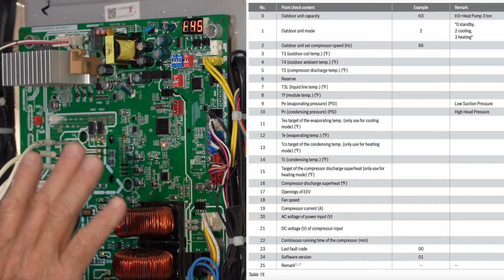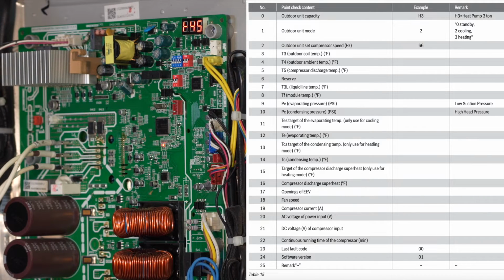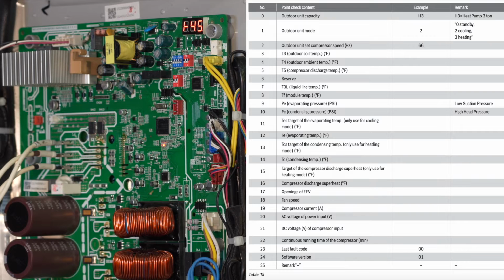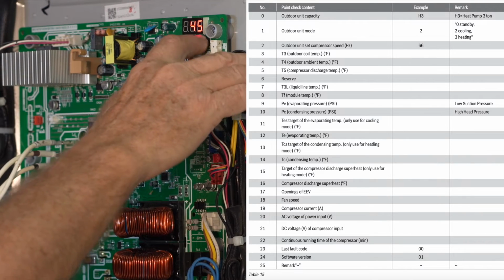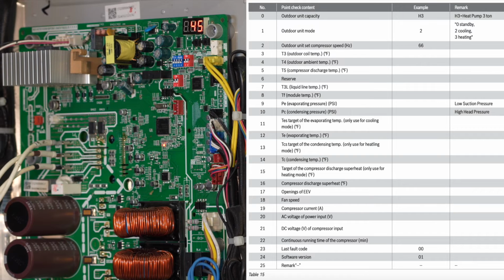Now, right now we're in the force mode. The force mode would stay there for 2 hours. If I forgot about the force mode and we just left and it's there, it's going to come out automatically in 2 hours. Or if I satisfy the thermostat, killing the Y call, we're back to normal operation. Or when I'm said and done with all of my parameters, my subcooling, my superheat, I can push that button one more time. It goes out of force mode, back into normal mode. We just did it, so that the unit would scale down a little bit and be quieter.